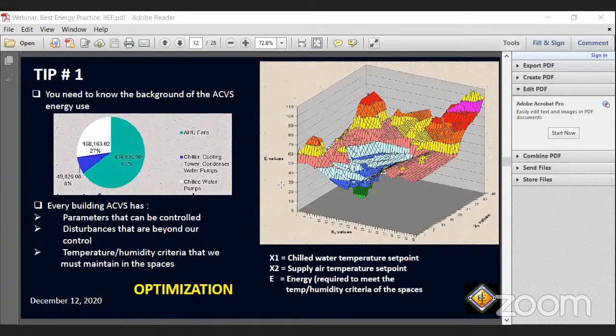Yung right na graph, yung three-dimensional profile, parang represent ito ng isang valley. Meron dyan yung X1, set point mo for the chilled water temperature. Yung X2 mo, set point mo for the supply air temperature. Tapos yung E, that is the energy required para ma-meet yung temperature, humidity criteria ng spaces mo. Ang target mo dapat ay ma-achieve yung pinaka mababang valley, yung green.